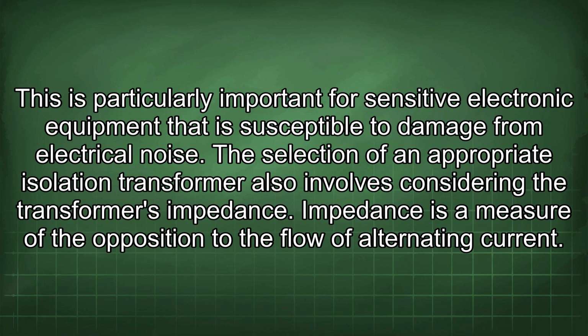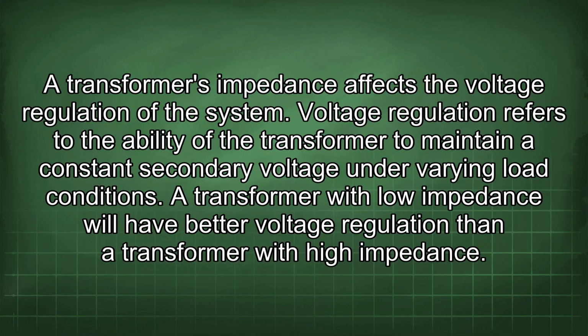The selection of an appropriate isolation transformer also involves considering the transformer's impedance. Impedance is a measure of the opposition to the flow of alternating current. A transformer's impedance affects the voltage regulation of the system. Voltage regulation refers to the ability of the transformer to maintain a constant secondary voltage under varying load conditions. A transformer with low impedance will have better voltage regulation than a transformer with high impedance.